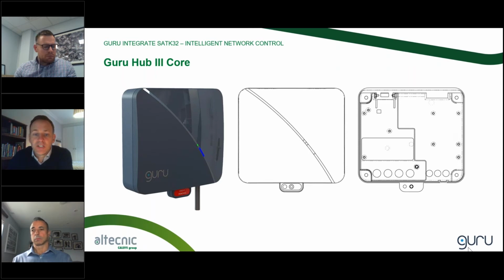A little bit more detail on those connections. On the MBus, you can hook up to 8 utility meters, and on Modbus, I'm told we can go to 250. We haven't tried that, or I haven't seen it done. They've done it on the bench. Pulse input, we would take 1, and the most common application that we see is when you've got AMR fitted to like a gas meter in a plant room or something that will only ever get you a pulse output. So we can happily take that.